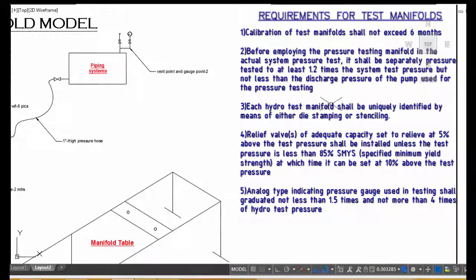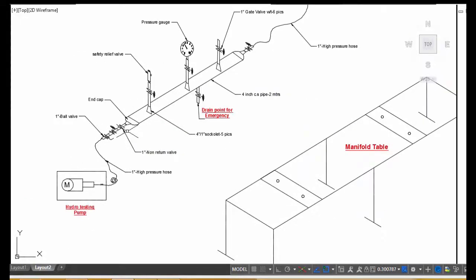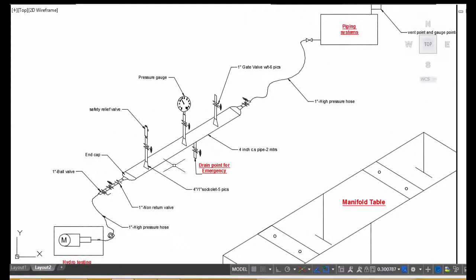For example, 100 bar means you have to test this manifold at 100 into 1.25 times for a 100-bar line.